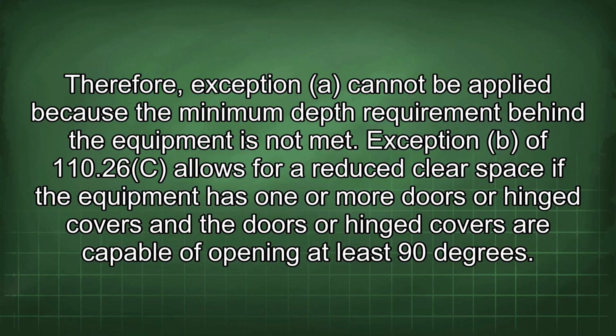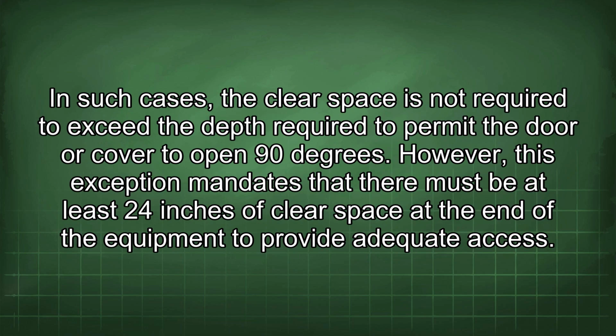Exception B of 110.26(C) allows for a reduced clear space if the equipment has one or more doors or hinged covers and the doors or hinged covers are capable of opening at least 90 degrees. In such cases, the clear space is not required to exceed the depth required to permit the door or cover to open 90 degrees. However, this exception mandates that there must be at least 24 inches of clear space at the end of the equipment to provide adequate access.